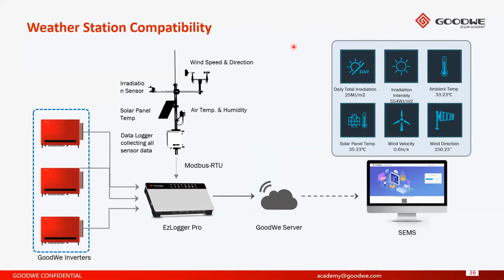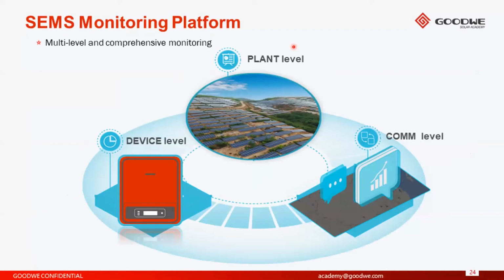Which leads me on to the SEMS portal, which stands for Smart Energy Management System, which is our GoodWe internal monitoring platform, which takes all the inverter information and displays it onto the SEMS portal. This allows you to monitor your PV plant in terms of the performance and any faults that may occur. And it is also useful for monitoring a fleet of PV plants. So if a customer or a developer is developing many PV plants and an O&M company has many PV plants under their control, they're able to view the performance of each of their PV plants under the one platform.